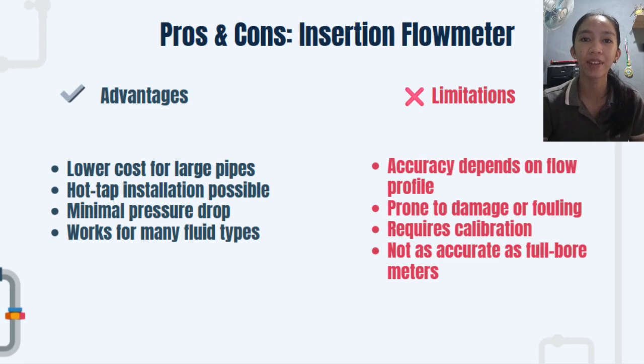Now, let's talk about the advantages of insertion flow meters. First, significant cost saving, especially on large lines. Second, the ability to be installed without shutting down the process. Third, they create only minimal pressure drop in the pipe. And lastly, they're versatile across many fluid types.